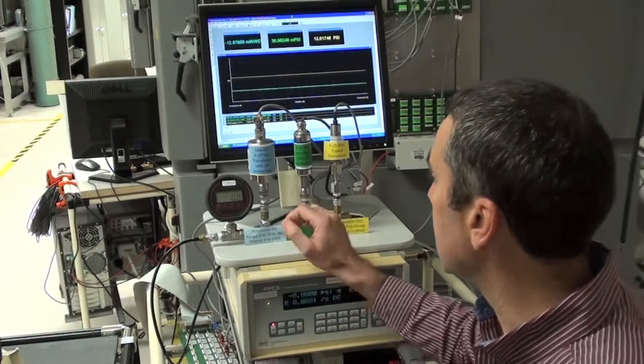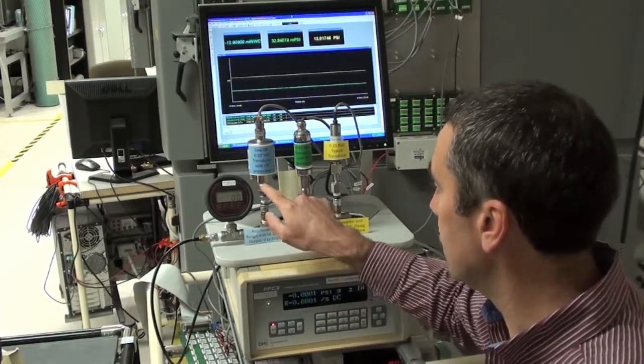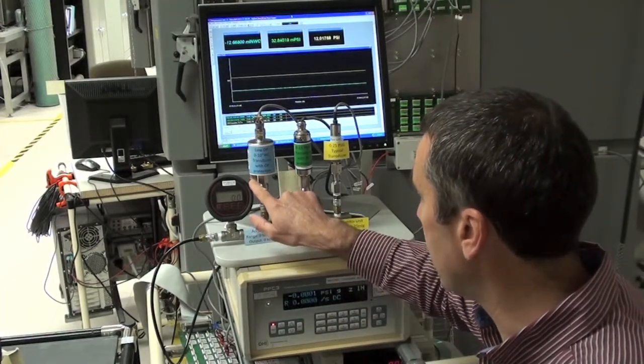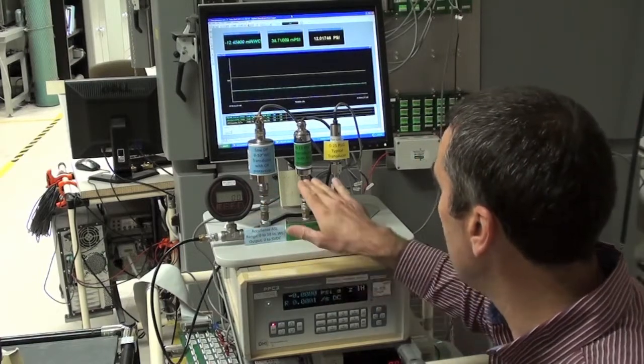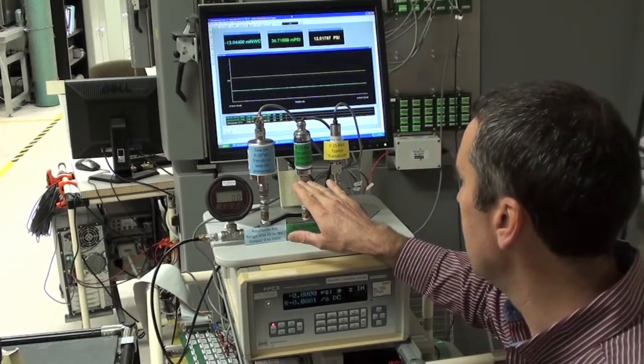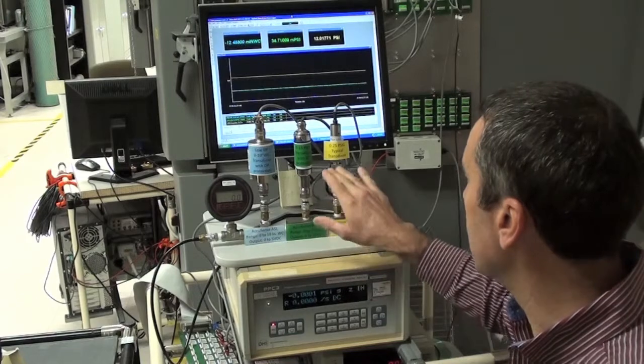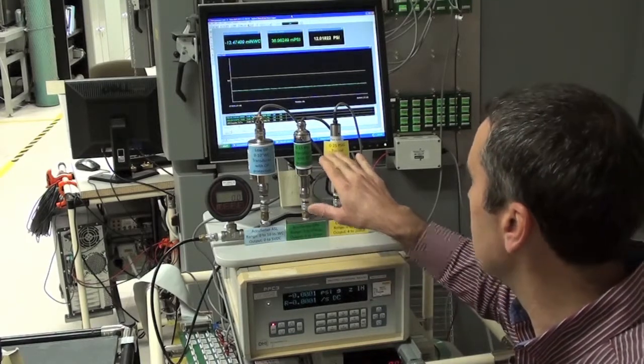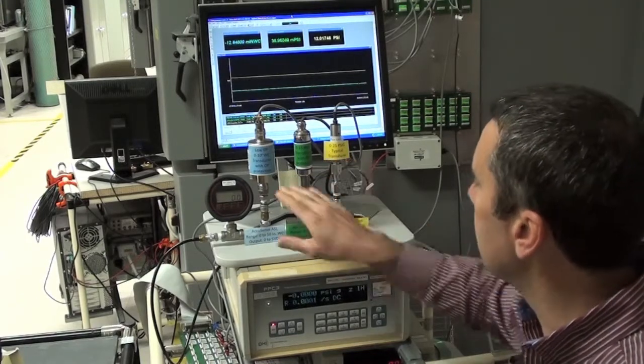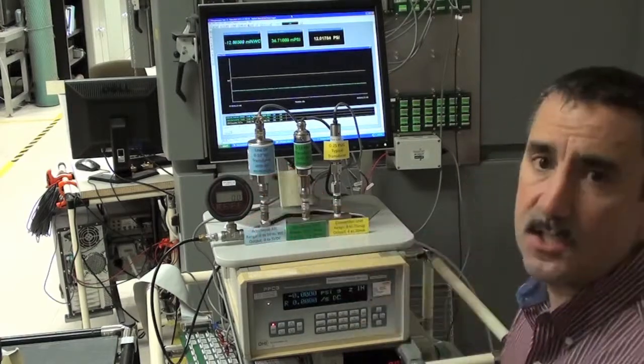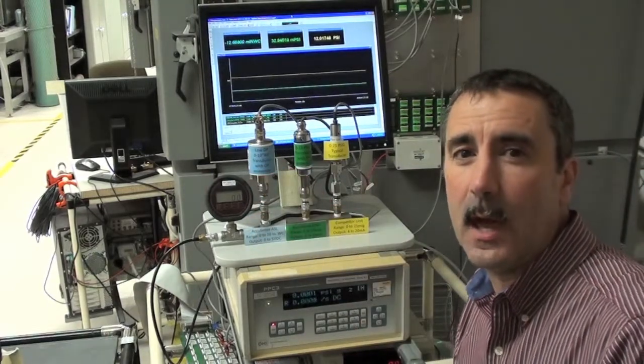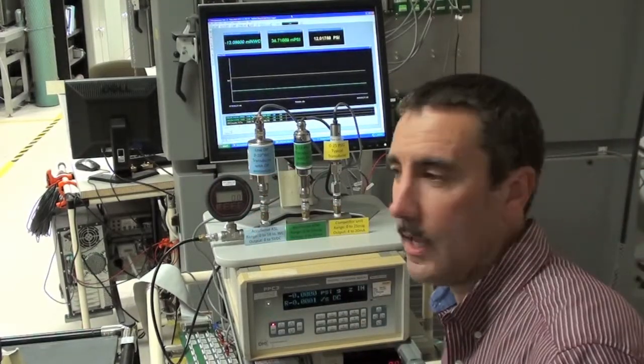This unit is a differential pressure transducer. You can see there's a reference port on there. This one is a gauge pressure transducer, 0 to 15 psi. This one is a gauge pressure transducer to 25 psi-G. The differential one is the lowest range. It's 10 inches of water column, roughly 0.36 psi.